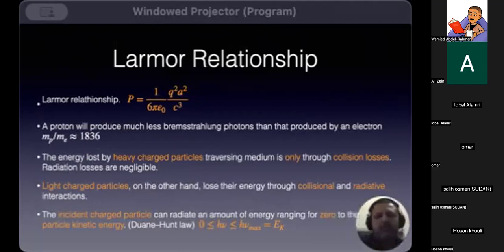when we look at a PDD for an electron beam, there is a Bremsstrahlung tail. And we know these are those produced by photons. These photons are produced from anything the electrons are going through when they come out from the waveguide and the bending magnets. So they will go through scattering foils, for example. They will go through the air. They will go through the monitoring chamber, and even the patient.